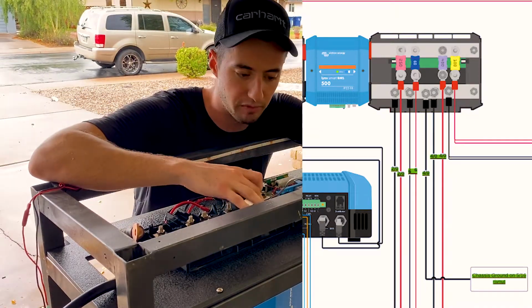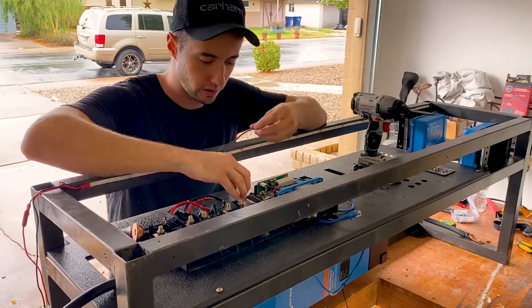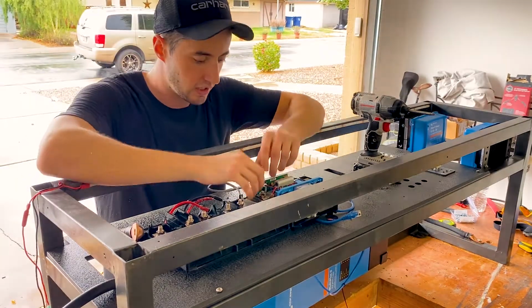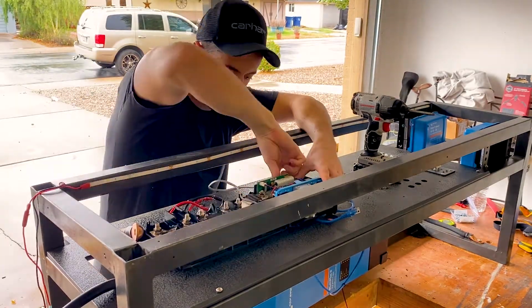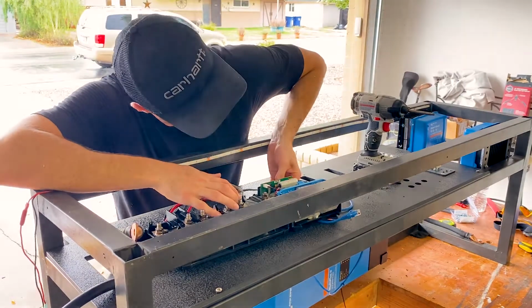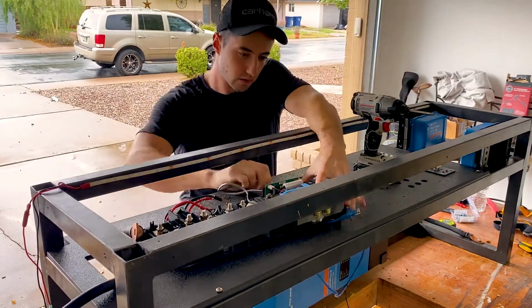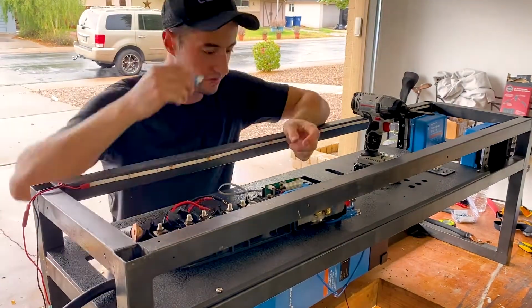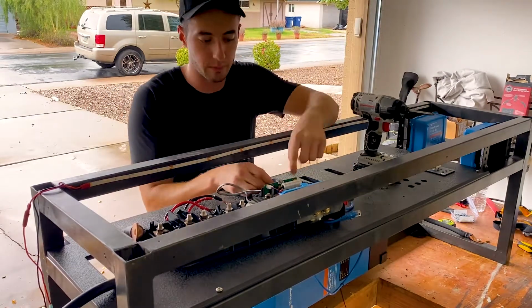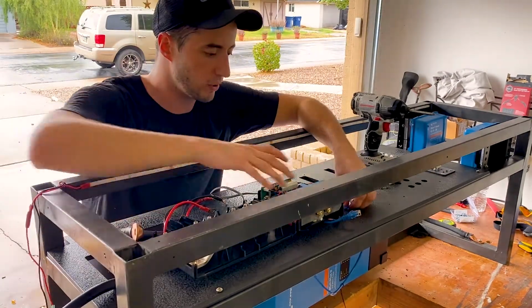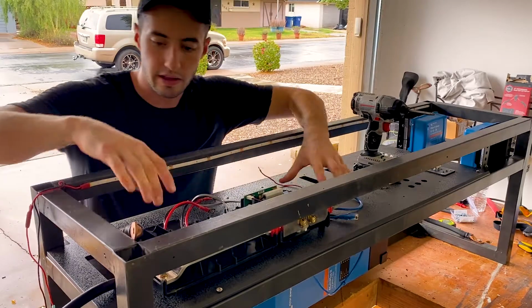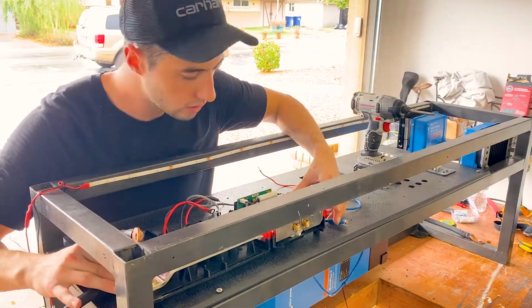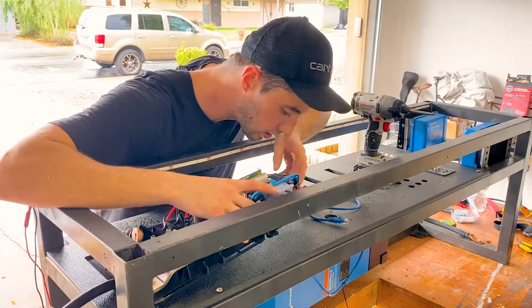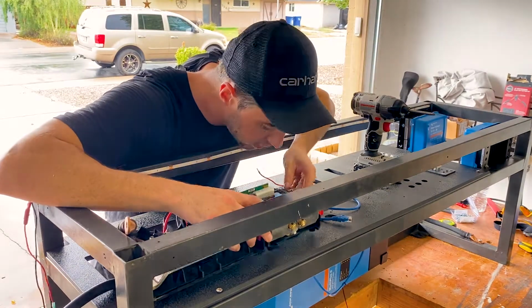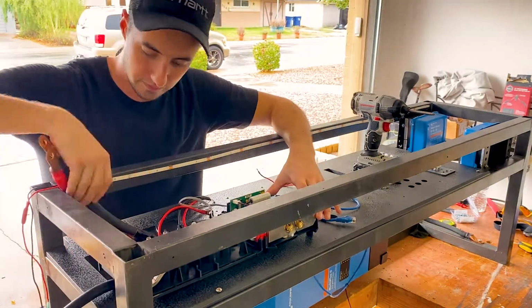You'll see this little gray wire here. There's a connection inside the distributor on the far left side. That wire will get plugged into the distributor and then across into the Lynx Smart BMS 500. This is what will enable communication between the distributor and your BMS, and will allow for the LED indicators, and also, if a fuse ever pops, you'll get the indicators on the GX Touch 50 display screen.